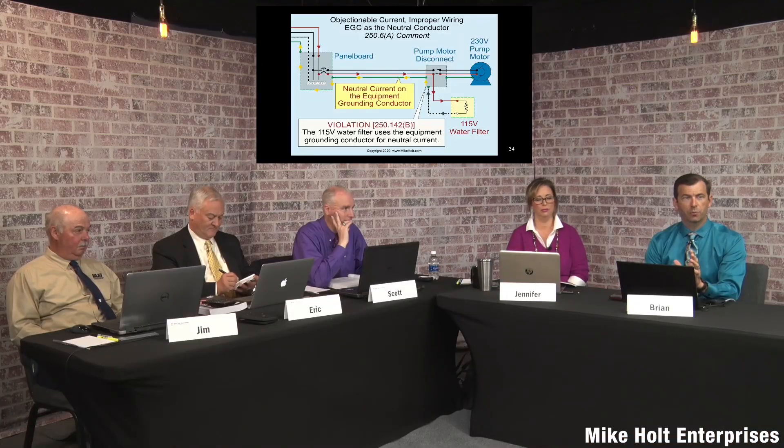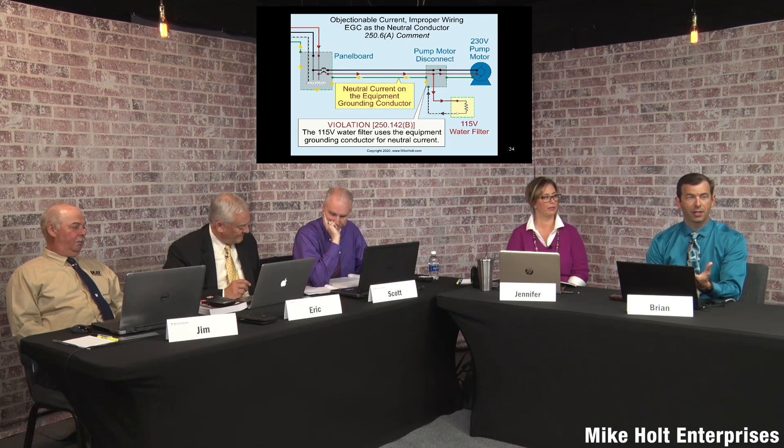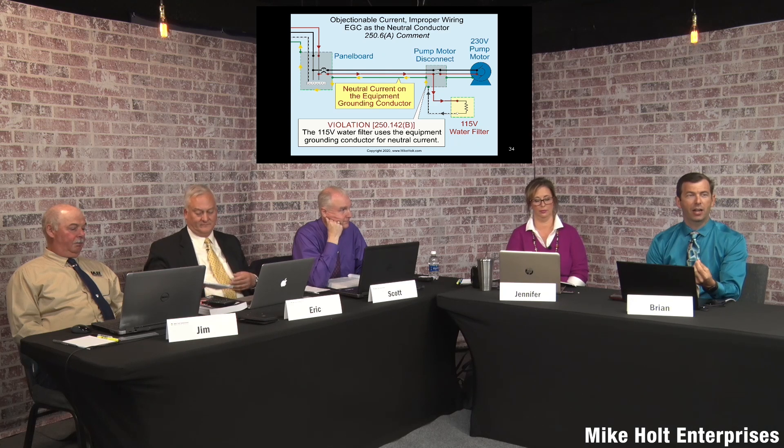A voltmeter measures the difference of potential — the difference between two points, not the same point. Take a voltmeter and connect it to the same terminal in a panel — what does it measure? Zero, because you're touching the same point. The white wire doesn't appear to have any voltage on it, but it is carrying current. All of the voltage has been consumed by the time it gets to the neutral bus, but if you disconnect the circuit you have all the voltage again because it's not a complete circuit — very confusing.